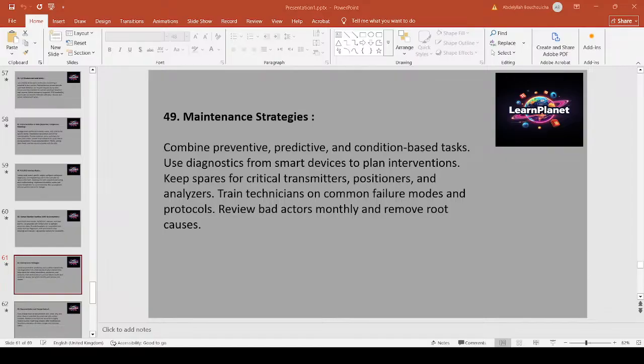Blend preventive, predictive, and condition-based maintenance. Use diagnostics from smart devices to schedule interventions and reduce unnecessary outages. Keep critical spares and have swap-out plans for high criticality transmitters and positioners. Train technicians on failure modes and root cause problem solving. Track bad actors monthly and apply corrective actions. Example: use valve positioner diagnostics to schedule replacement of a sticking valve before it causes a process upset.